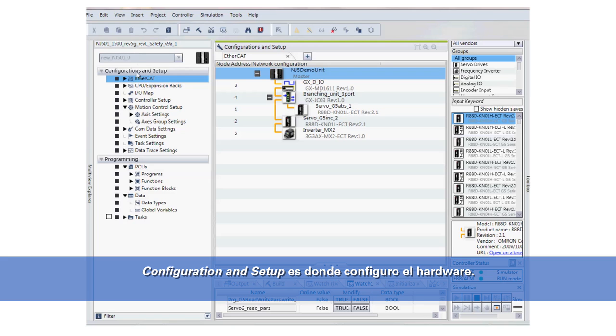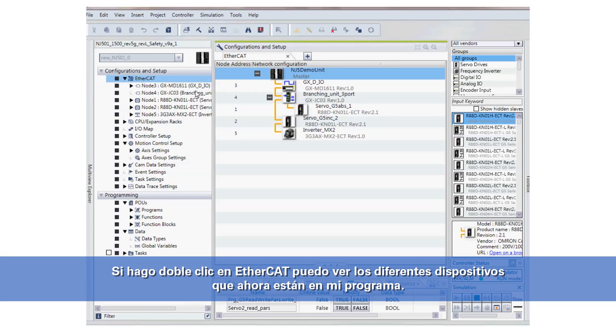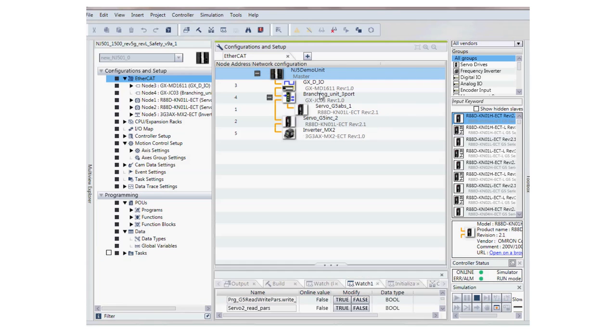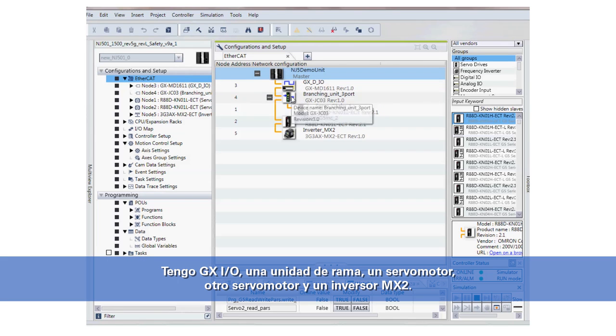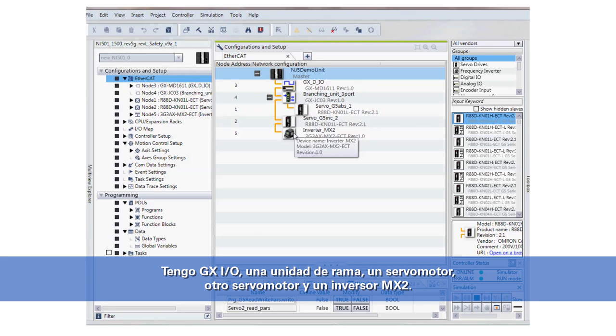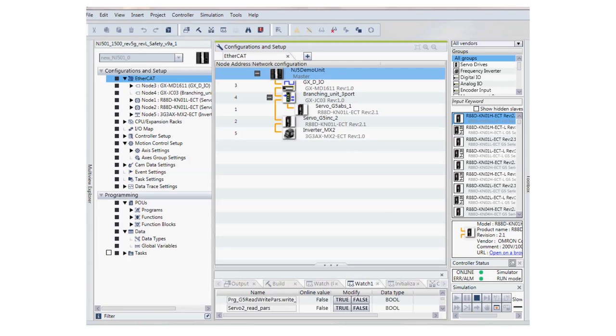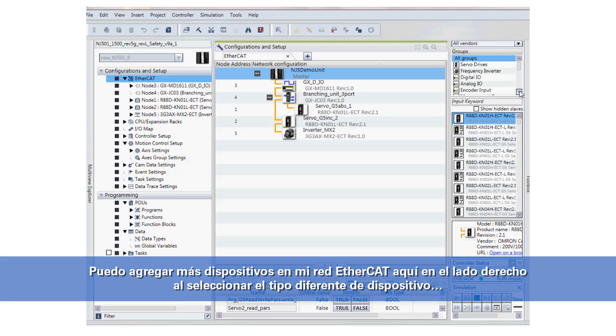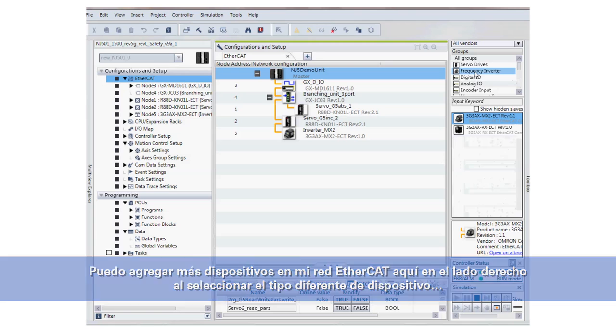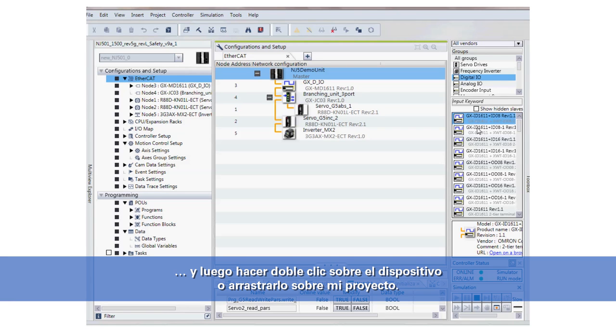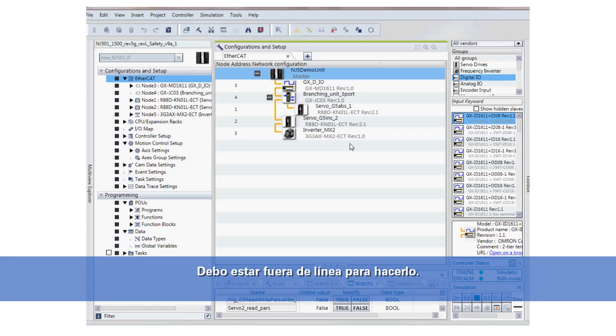In the configuration and setup, this is where I set up my hardware. If I double-click on EtherCAT, I can see the different devices in my program: I have GXIO, a branching unit, a servo motor, another servo motor, and an MX2 inverter. I can add more devices to my EtherCAT network on the right side by selecting the type of device, then double-clicking on it or dragging it over to my project. I have to be offline in order to do that.